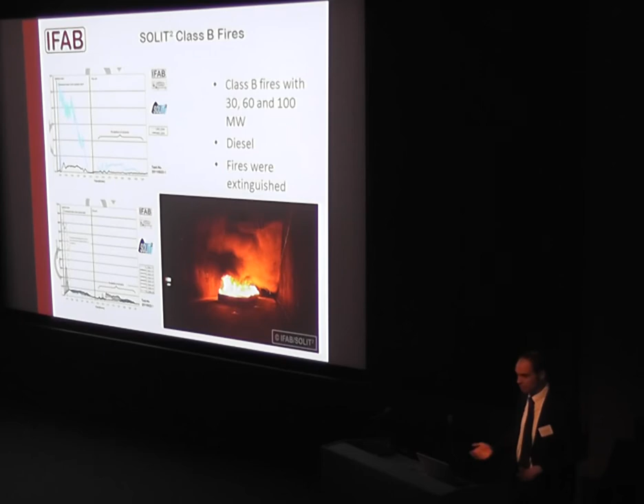It's quite the same picture when you look at Class A fires, and that's of course one of the things which always leads to strong discussions about these systems. Usually your fire load is fully covered. Look at your trucks on the roads, they are covered. Almost in no case is the fire load open, or maybe just the outer areas are open, but you cannot really introduce your firefighting agent into the fire. That's absolutely impossible, just from physics. You can do this with the firefighting tools, because you use much more water and you can really point your water where it's needed, but with an automatic system, it's not possible.